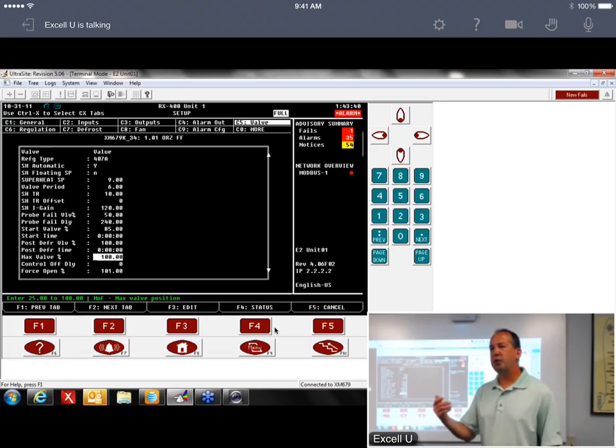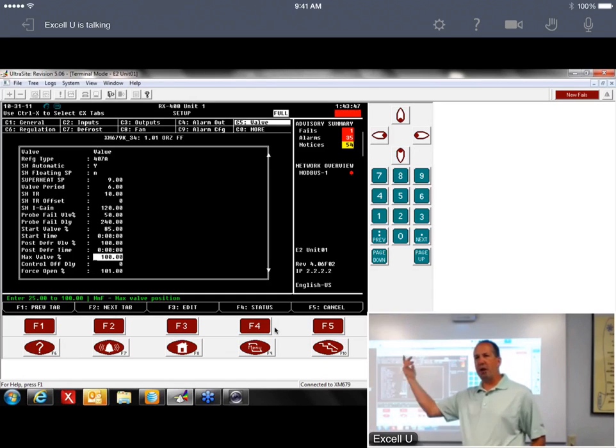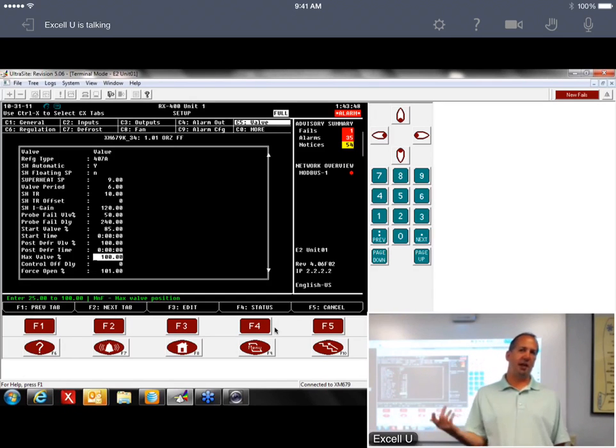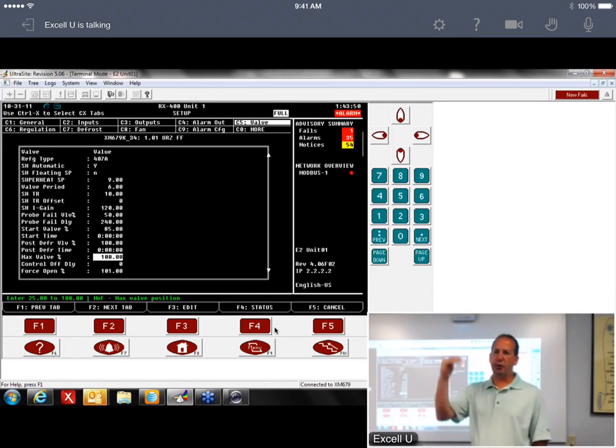So what you'd want to do is graph your valve percentage, and you'd actually want to see the valve percentage kind of bouncing somewhere, 40, 50, 60%, something like that. If it's 0, 100, 0, 100, 0, 100, that's when you want to look at changing your max valve percentage. So.